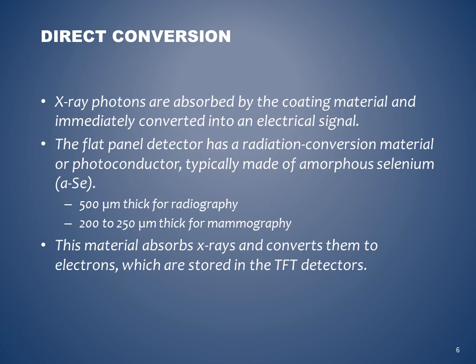The flat panel detector has a radiation conversion material, a photoconductor, typically made of amorphous selenium. So again, a test question might consist of: the flat panel detector may be typically made of amorphous selenium, or we can see it as a-Se. It's usually about 500 microns thick for radiography or 200 to 250 for mammography. This material absorbs X-rays and converts them to electrons, which are stored in the TFT detectors.